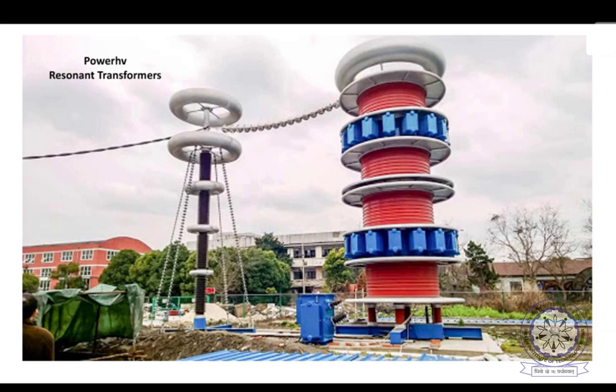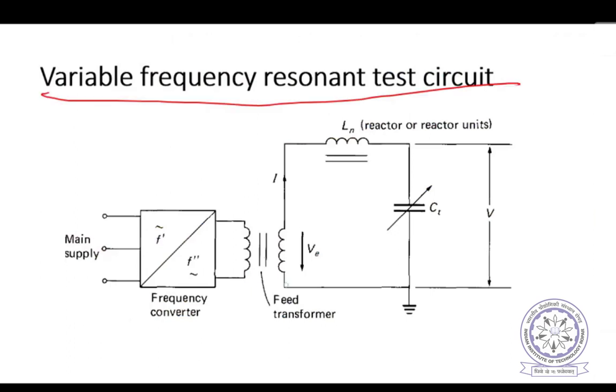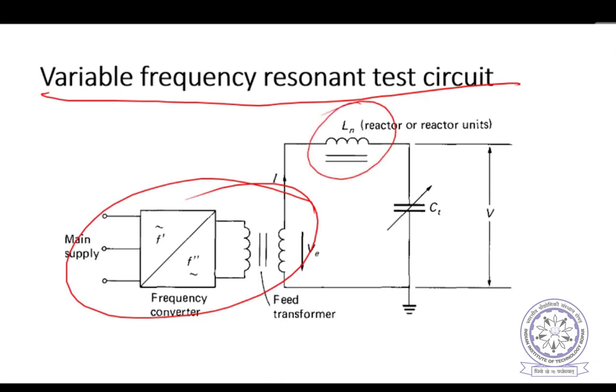Now, one more principle is variable frequency resonance. Instead of changing the inductance, change the frequency to achieve the resonance. Because if you go on increasing the frequency, omega L will be increasing and 1 by omega C will be decreasing. So at some point, these 2 reactances will be equal. That is the resonance condition. That's how resonance can also be achieved using variable frequency. But of course, there are concerns that you are not testing at the power frequency. Normally power equipment operates at power frequency, so that is one of the disadvantages of this.